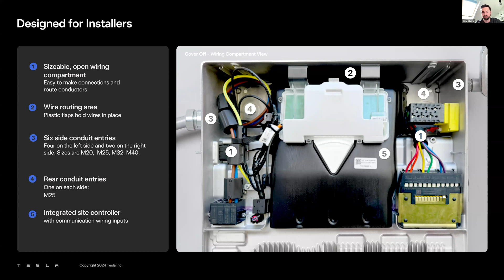In the middle is the board. We call it the TACO, the Tesla Asset Controller. Now, the board previously in Powerwall 2 was in the gateway. It's now sited inside the Powerwall, so all your commissioning is done at Powerwall level. You scan the QR code, as you can see in this image, and that starts the commissioning process. So all the clever things are now done at Powerwall level.